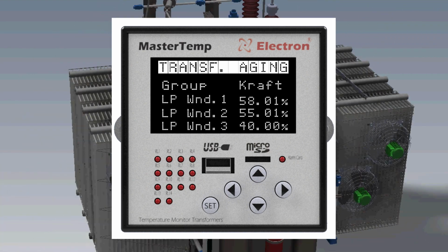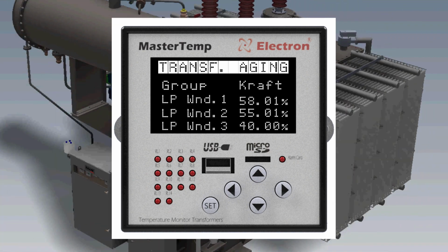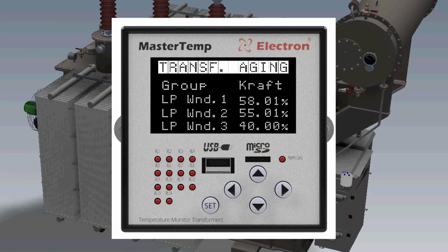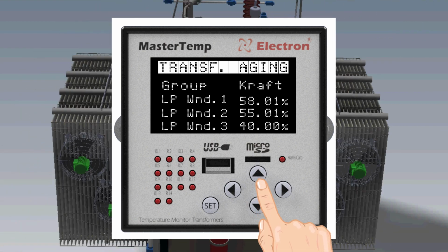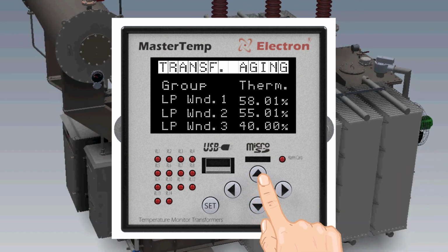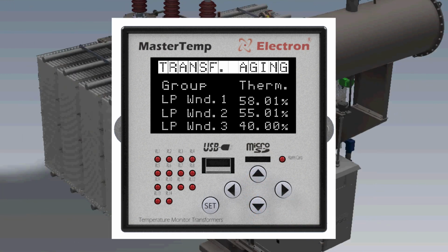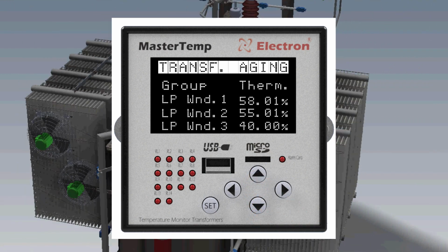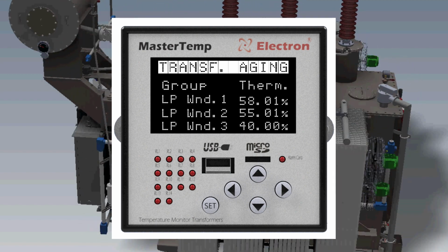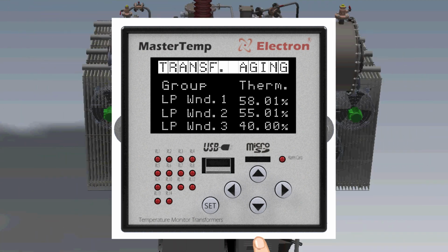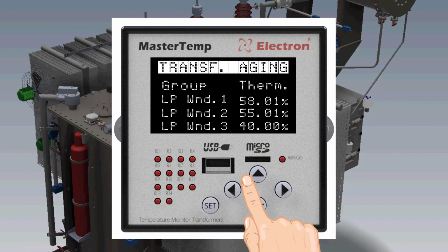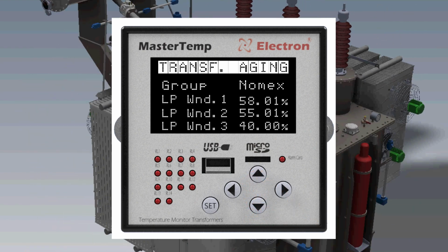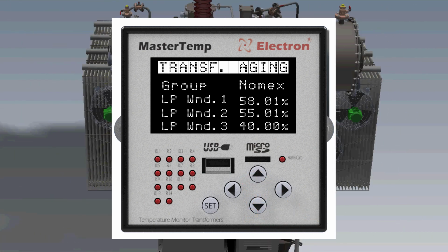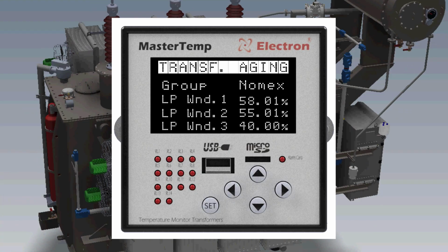That is, kraft, for transformers with a temperature elevation factor of 55 degrees Celsius. Thermostable, for transformers with a temperature elevation factor of 65 degrees Celsius. Or NOMEX for transformers with temperature elevation factor of 95 degrees Celsius.